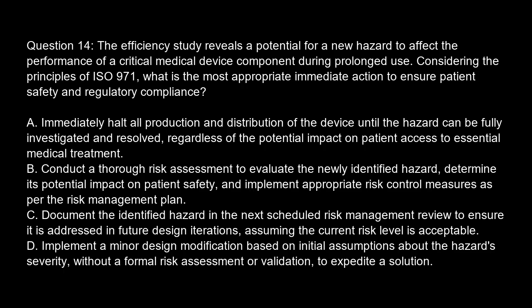Option B. Conduct a thorough risk assessment to evaluate the newly identified hazard, determine its potential impact on patient safety, and implement appropriate risk control measures as per the risk management plan. Option C. Document the identified hazard in the next scheduled risk management review to ensure it is addressed in future design iterations, assuming the current risk level is acceptable. Option D. Implement a minor design modification based on initial assumptions about the hazard's severity, without a formal risk assessment or validation, to expedite a solution.